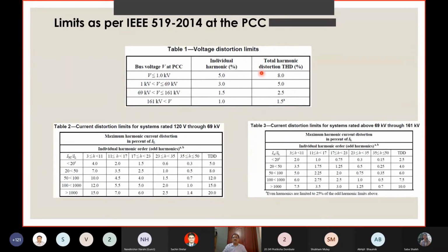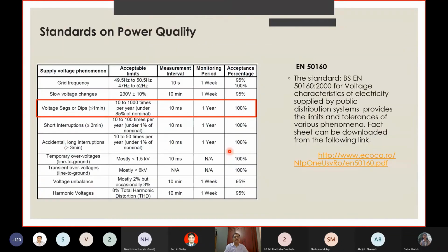But these are the 3 limits: total harmonic distortion voltage, individual voltage harmonic distortion, and the total demand distortion for current. These are the 3 limits. We'll see as we progress if we have some case studies to expand on this. This is the standard IEEE 1159 which I mentioned to you, and also EN 50160. This chart here from EN 50160 can be downloaded from this website, or you can find other sites also which can give you this.